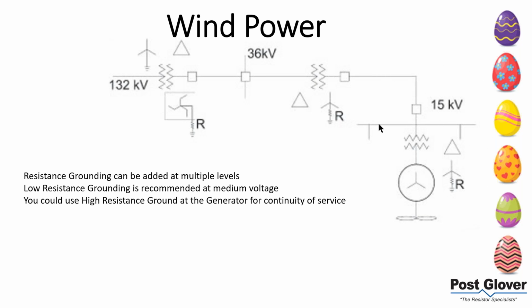We would definitely recommend low resistance ground at your medium voltage. Really, anything above 5 kV, there's not really a good case for high resistance grounds, especially in the type where you continue to operate. There are some applications where you would use that for just generator protection. You wouldn't necessarily be operating continuously, but the point is that usually 5 kV and below is where that's at. Anyway, even at the higher voltages in this picture, you talk about 36 kV, potentially you could use it.